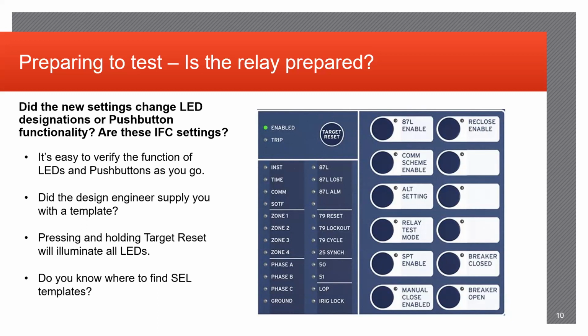Easiest way to go about it, if you do need to change the labels, would just be going onto the SEL website, going to the specific type of relay that you're going to be testing, and downloading either a Word document or PDF file of the label templates. And you can edit them from there, print them off. Usually the relays will be delivered, and the client may have extra templates on site for the specific material they use to put into the relay front panel itself, and then you can print those off and replace them if need be.